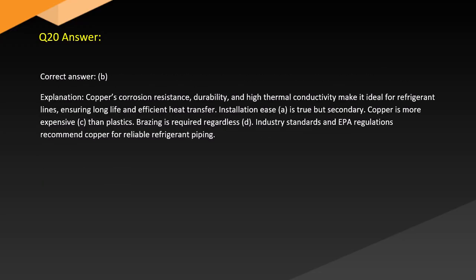Answer. Correct answer, B. Explanation. Copper's corrosion resistance, durability, and high thermal conductivity make it ideal for refrigerant lines, ensuring long life and efficient heat transfer. Installation ease is true but secondary. Copper is more expensive, C, than plastics. Brazing is required regardless, D. Industry standards and EPA regulations recommend copper for reliable refrigerant piping.